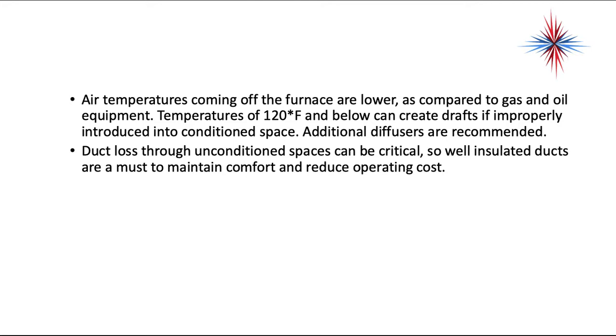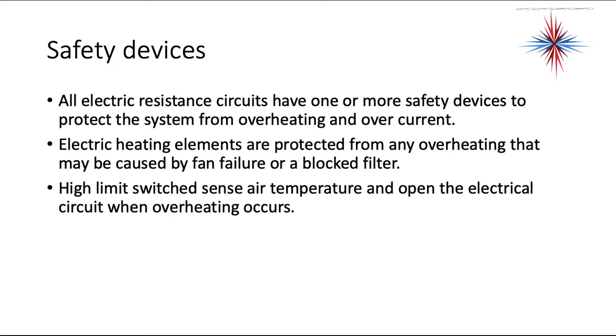Electric heat, when it first comes on, before it has a chance to warm the ducts, sometimes can be considered drafty. So a lot of times we run it at a lower blower speed, or we add additional diffusers in a room so that the drafts are less obvious.